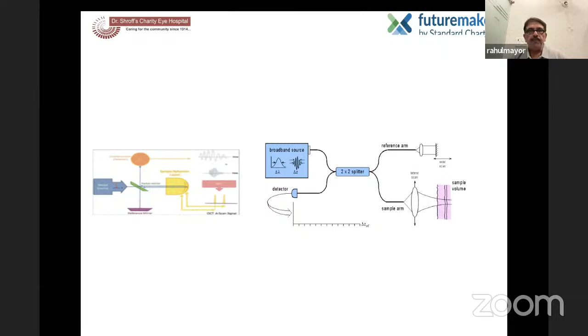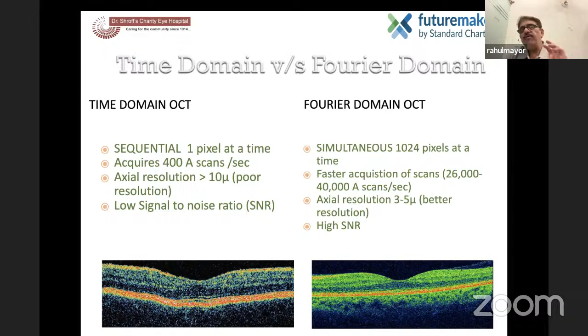So I'll take you back to the time domain OCT, which was in the mid 90s when this came into play. This used to take sequential, one pixel at a time, and acquires around 400 A scans per second. The axial resolution is poor, more than 10 microns, and it has a low signal to noise ratio. On the other hand, these days we have the Fourier domain OCTs, which take simultaneous 1024 pixels, faster acquisition, approximately 26 to 40,000 scans per second, a very good axial resolution of 3 to 5 microns, and a very high signal to noise ratio.